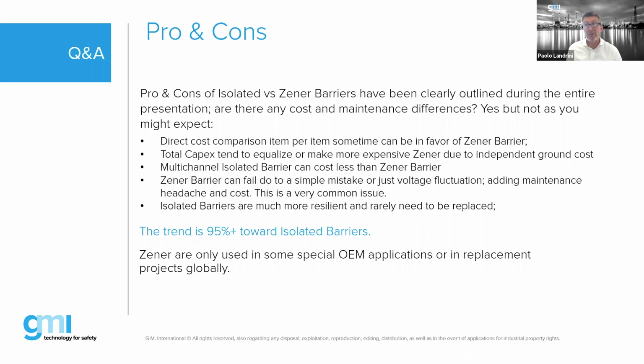Sometimes it can be the opposite of what you expect. When you look item per item, you buy a Zener barrier—typically you need a double Zener barrier because you have two wires, so you need two paths of protection. Versus an isolated barrier, the cost difference is there sometimes. An analog isolated barrier might cost more than a Zener barrier, whereas a digital isolated barrier might cost less than a Zener barrier. But in general, you might believe the Zener barrier is less expensive.